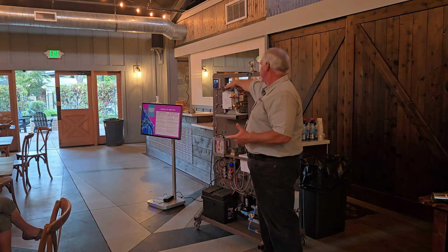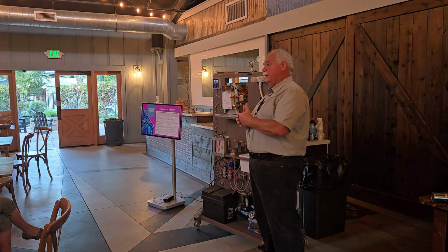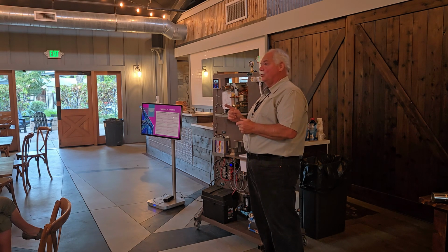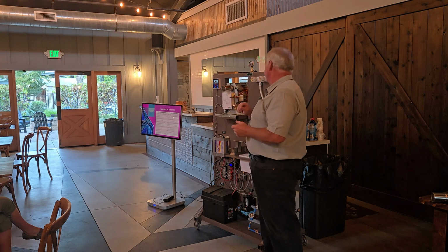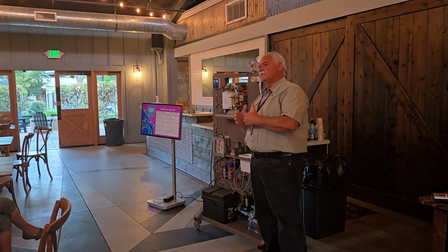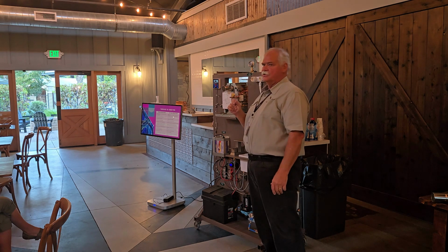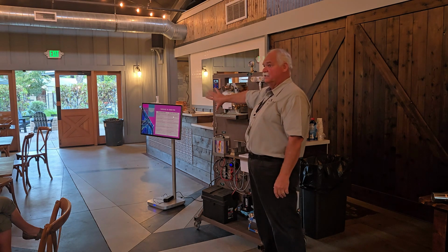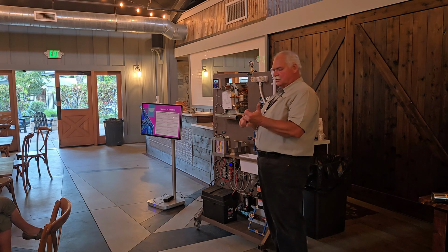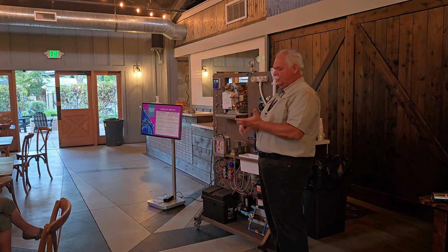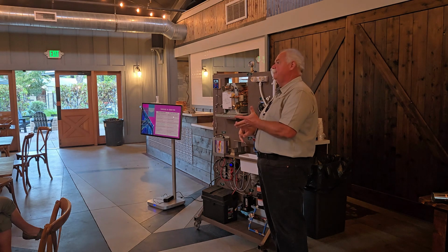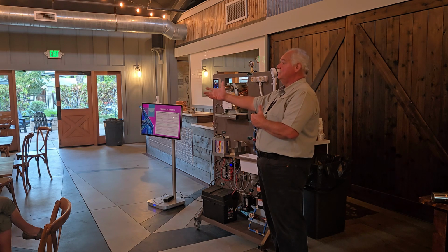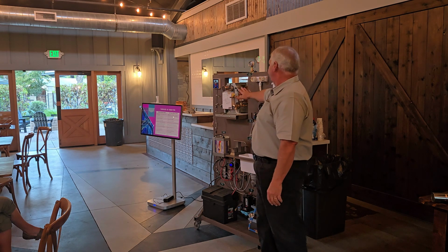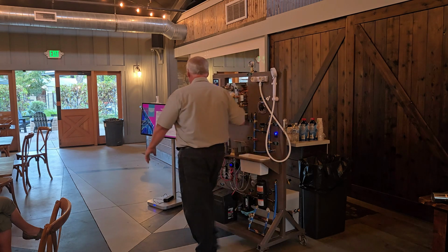Then we're going to check input and output temperatures to make sure that they're not above what this thing can run on. And yes, input temperature is important. So keep that in mind. Mainly output temperature, because if this thing gets above that 124 degrees, it's going to shut down. I have this set at 124. I leave this at the max for my demonstrations. So water flow, airflow, check the temperature incoming and outgoing. Then let's light that burner. And then let's wait a good 5 seconds for that heat to actually get to the water going through this.